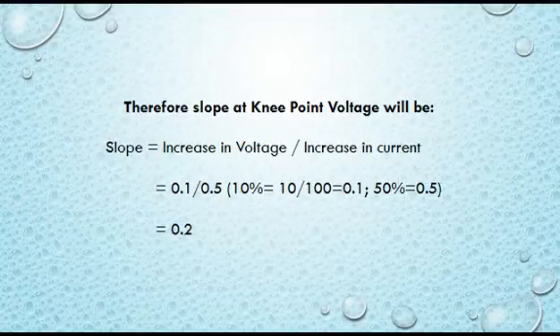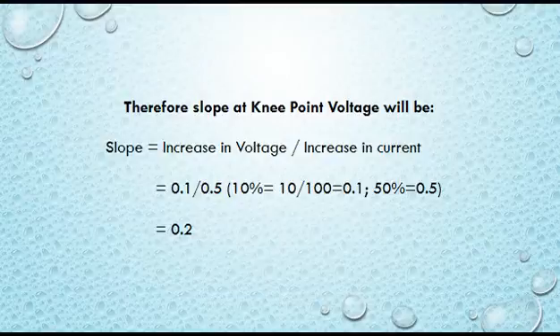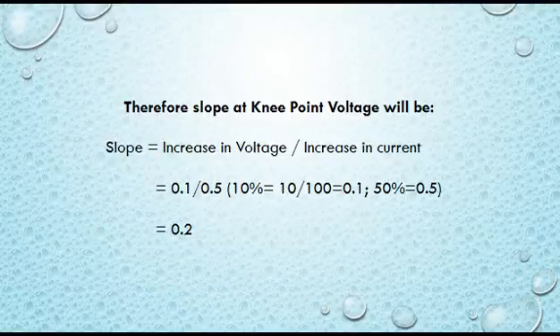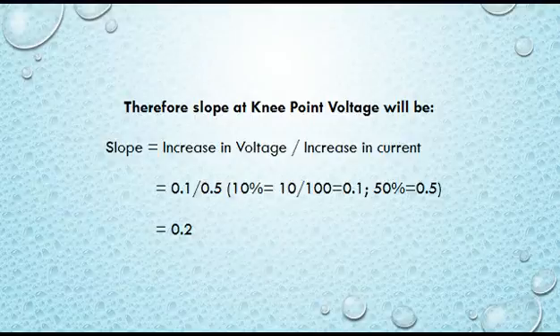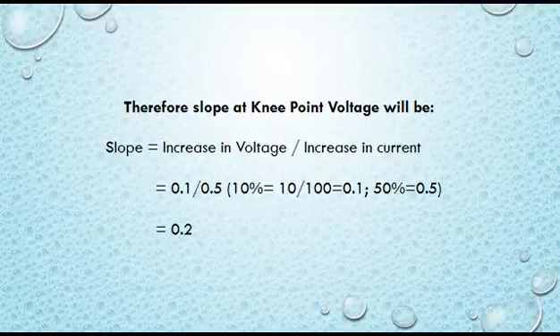Therefore, the slope at the knee point voltage can be calculated as: slope equals increase in voltage divided by increase in current, that is 0.1 divided by 0.5 — where 10% means 0.1 and 50% means 0.5. By division, the result is 0.2.